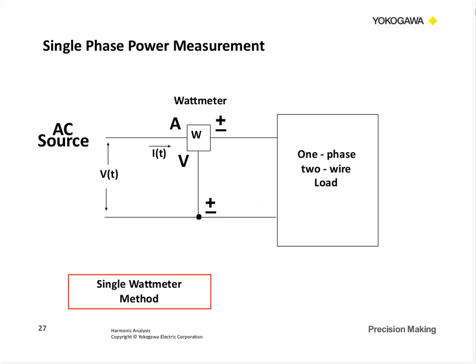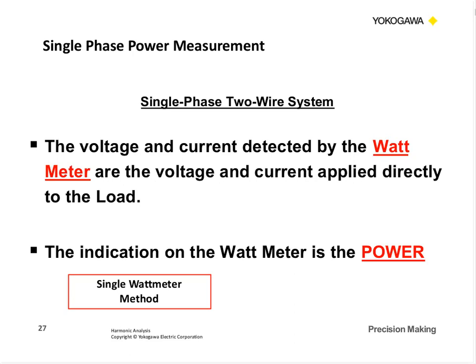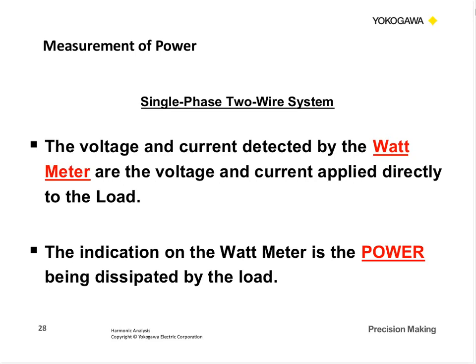So let's look at a quick single-phase measurement. We've got some type of load here. We've got an AC source out here. We put our wattmeter in line. We measure the current in series and the voltage from line to line. You'll notice there are some markings showing the polarities. These are instantaneous polarities. It's very important that you follow the manufacturer's wiring diagram and these polarities for the instrument. If you get some of these turned around, you may get a negative power reading, and that's not going to be correct. So make sure you follow whatever the manufacturer's wiring diagram is, and how they indicate those. So on a single phase 2-wire system, it's very simple. The wattmeter just shows the power that's dissipated by that load. We measure the voltage and the current applied directly to the load, and then that power measurement is actually that being dissipated by the load.